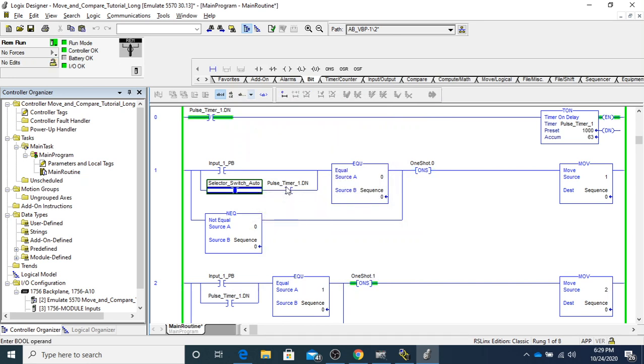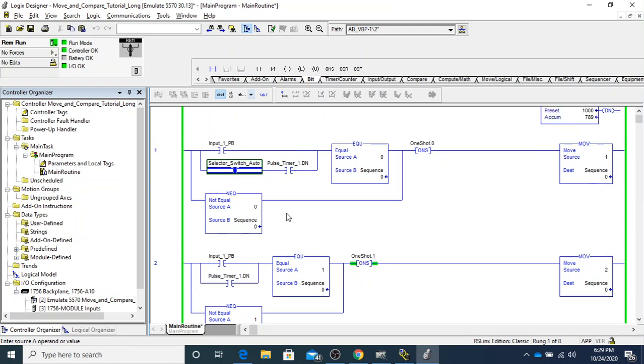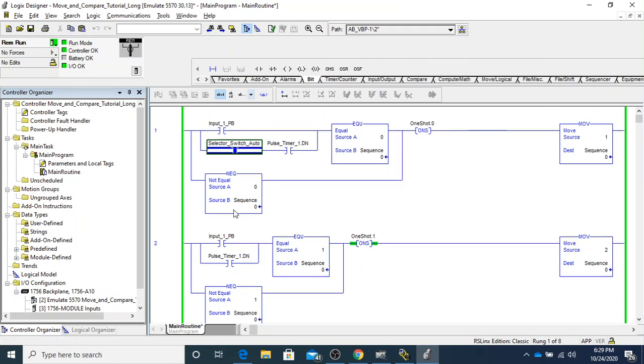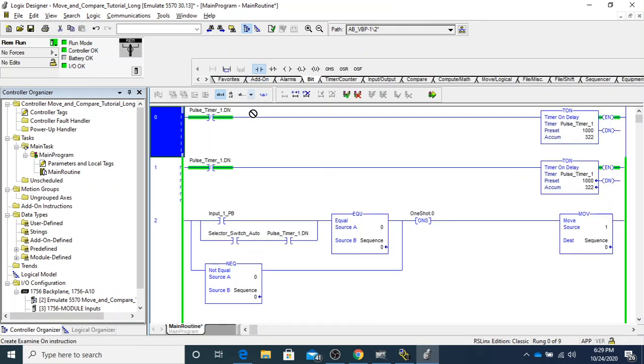So if I interrupt it here, it interrupts it everywhere, because this right here never goes through. Now that's kind of dirty. I would rather go ahead and put it in every rung, because you don't know where it's going to stop at.